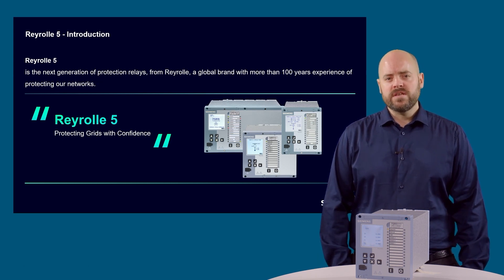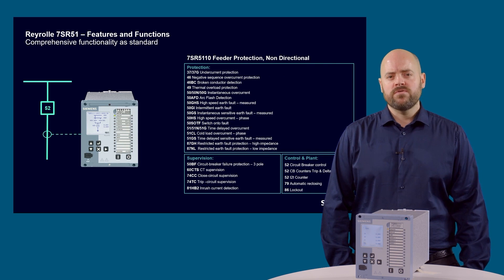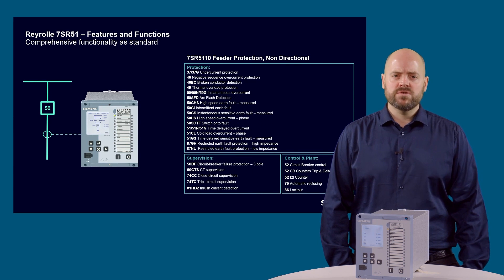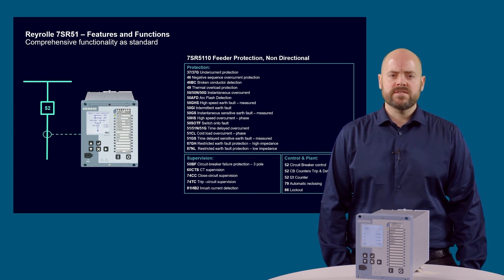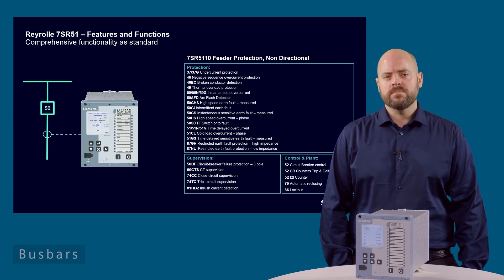Let's take a look at the features and functions that the 7SR51 offers for feeder protection applications. The Reyrolle 7SR5110 devices provide the primary function of overcurrent and earth fault protection functionality for medium voltage substations, as well as backup protection for other main protection devices — for example on lines, transformers, generators, motors and busbars.